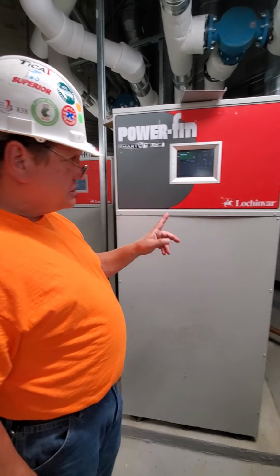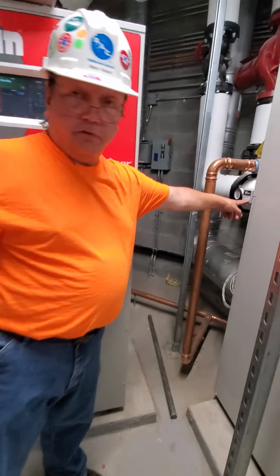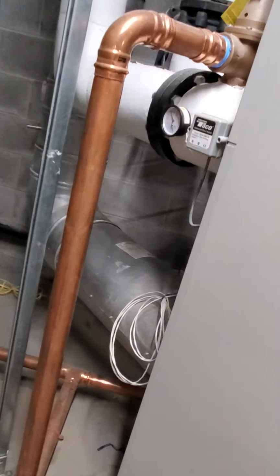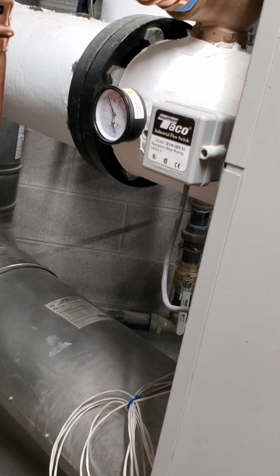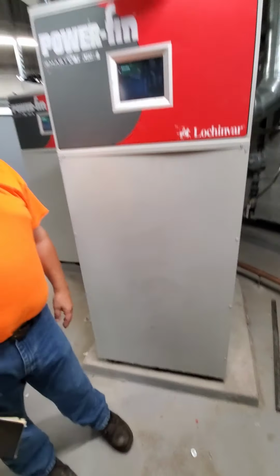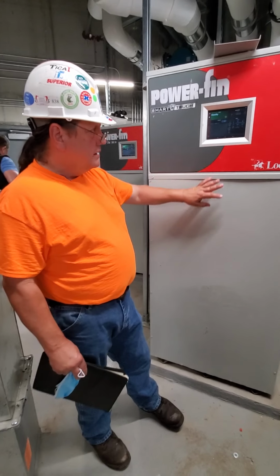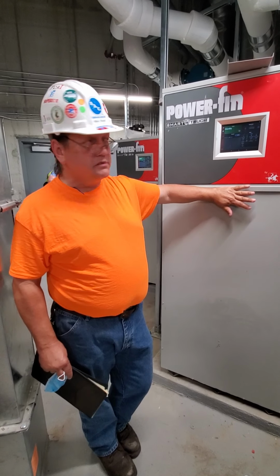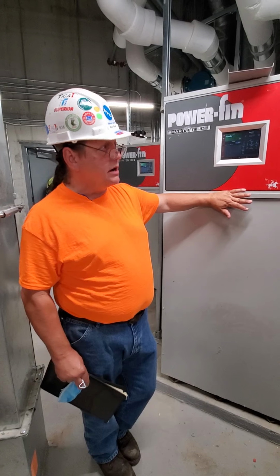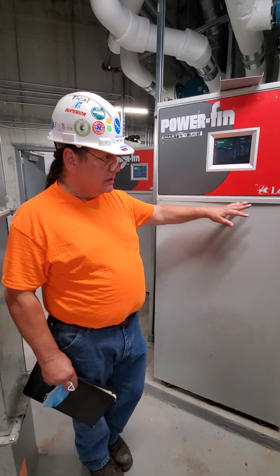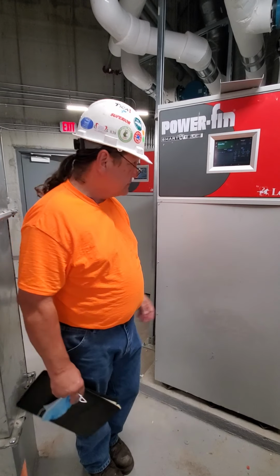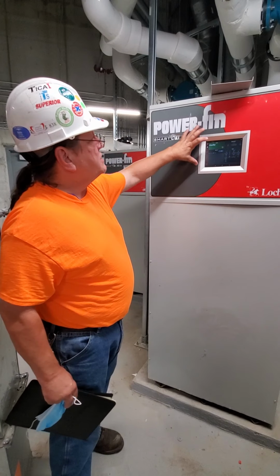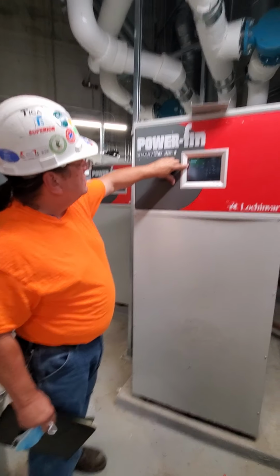There is a flow switch on each boiler. Here's the flow switch. So if the pump does not run, that is the switch that is not being turned on. Or that switch itself could fail. There's a numerous amount of items that could be causing that to lock out. System actually low on water, pump not running, pump running the wrong direction, failure of the flow switch. I said these boilers will tell you exactly what's going on.